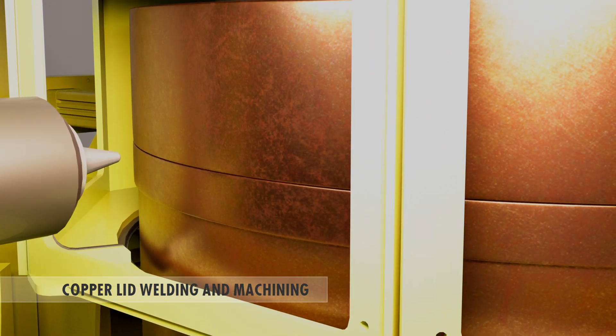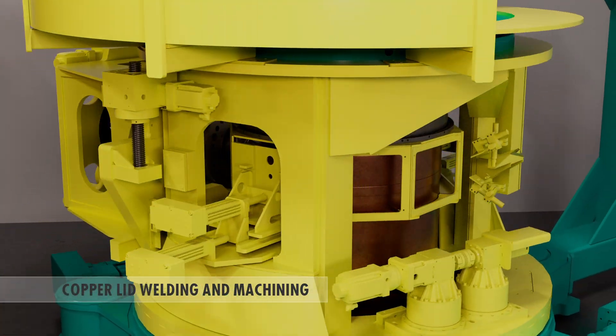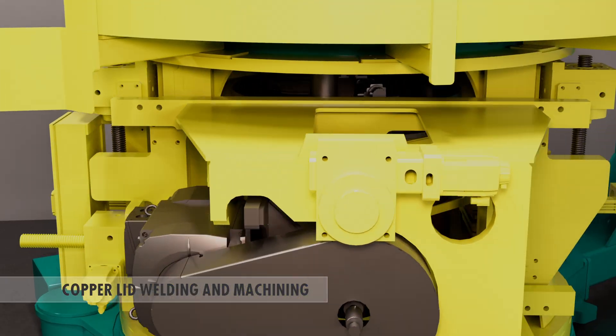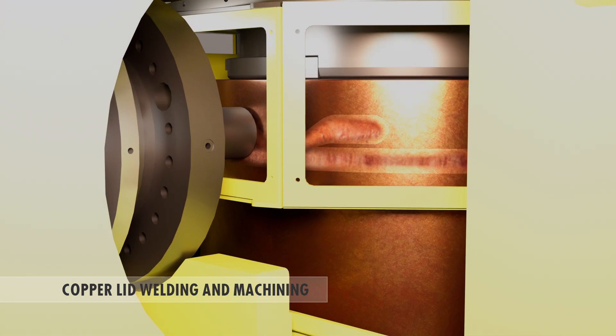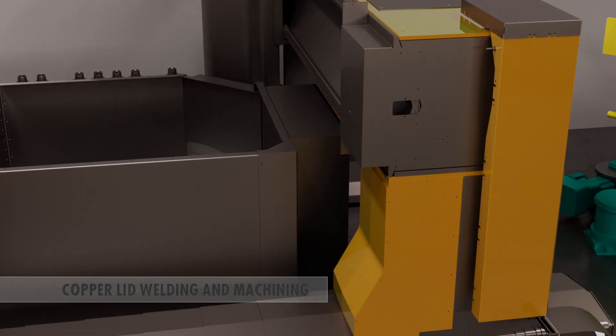After welding, the canister is returned to the machining station, where the upper end of the canister is machined. Machining removes excess copper from the canister lid and machines the weld seam area to allow inspection of the weld by eddy current and ultrasound testing, in addition to visual inspection.